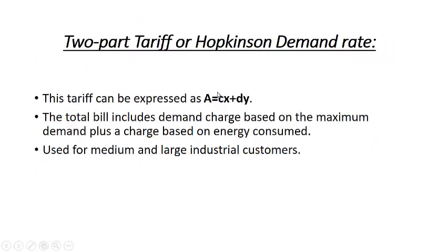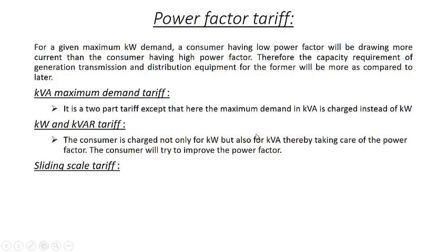In the two-part tariff here, this X is the maximum kilowatt, but in case of power factor tariff, this X is replaced by the kVA, or we can say maximum demand in kVA instead of maximum demand in kilowatt. So it takes care of the power factor itself. Or if kilowatt is charged and we charge kVAR separately, both charged separately, then also the power factor is taken care of. So the consumer is charged not only for kilowatt but also for kVAR, thereby taking care of power factor as well.